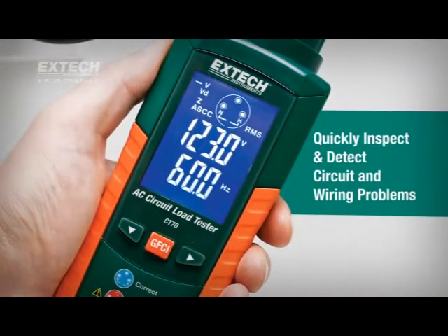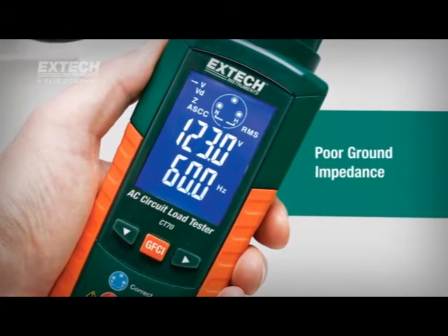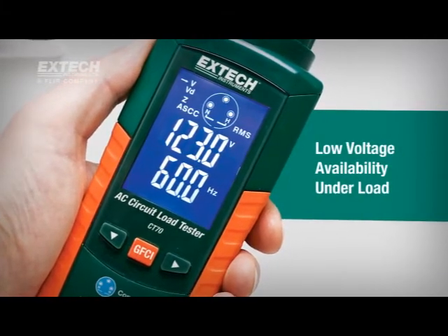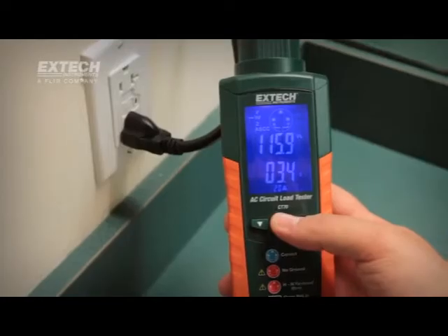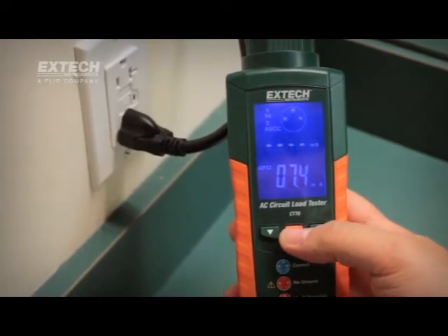The Extech CT70 quickly inspects and detects circuit and wiring problems such as poor ground impedance, false grounds, missing ground fault protection, low voltage availability under load, and high ground to neutral voltage. In addition, the CT70 tests GFCI and EPD circuits.